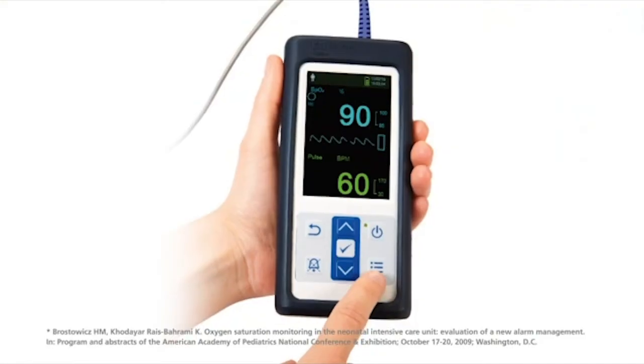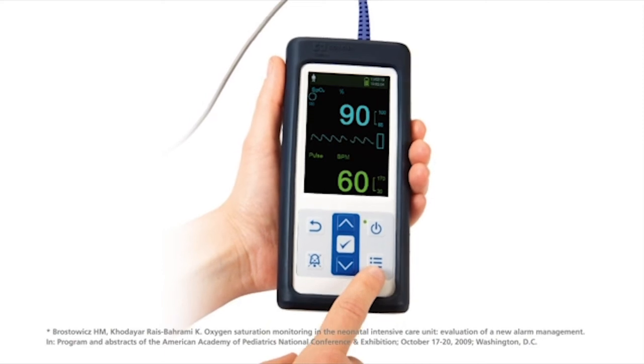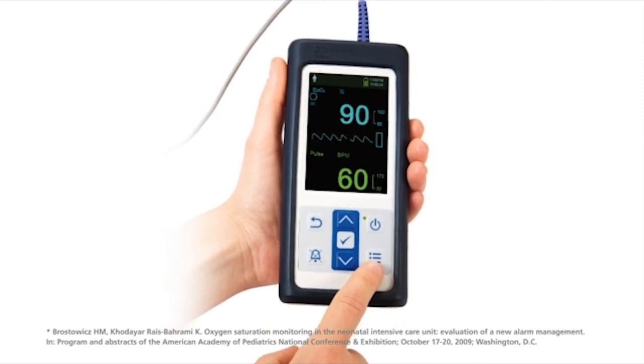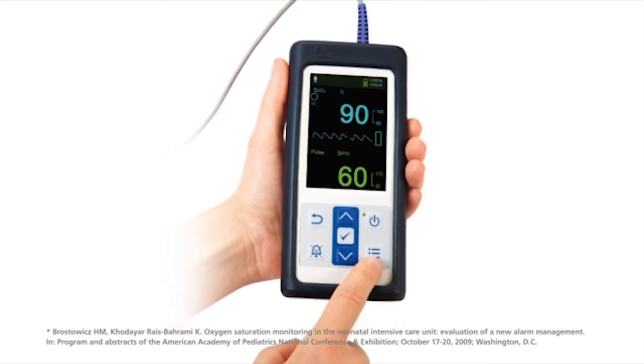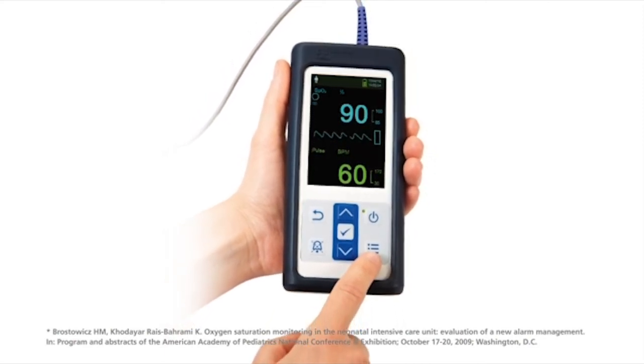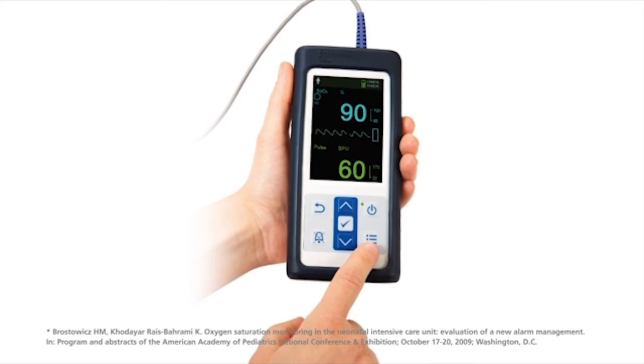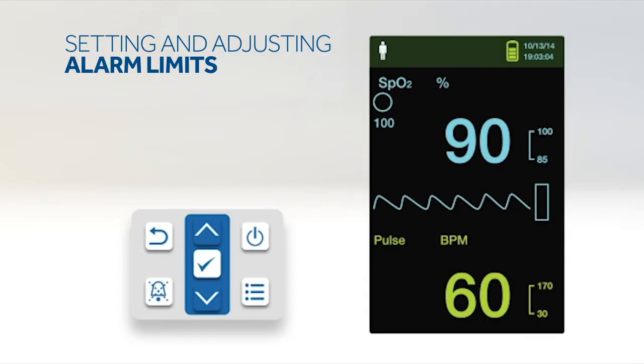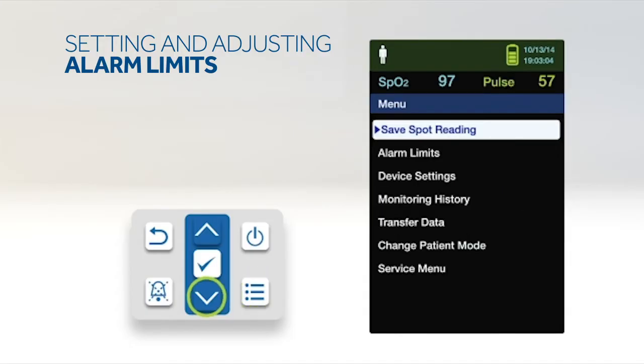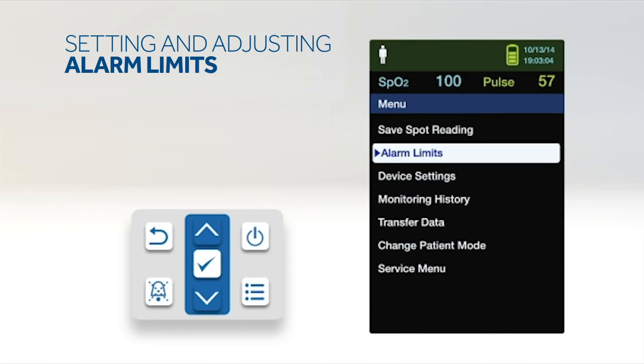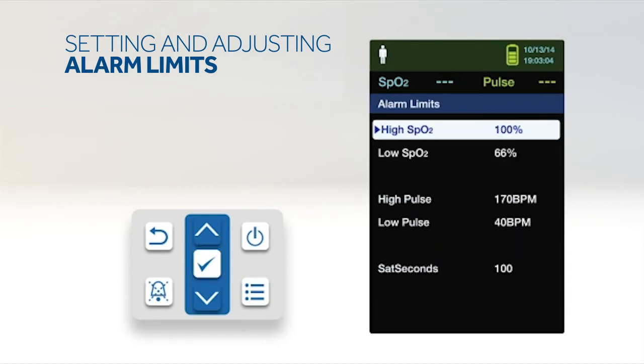An alarm management system analyzes the SPO2 events to avoid triggering alarms unnecessarily. The PM10N incorporates this alarm technology, Nellcor SatSeconds, to reduce nuisance alarms. To set alarm limits, press the menu button. Press the down button to highlight the alarm limits menu item and press OK to select.